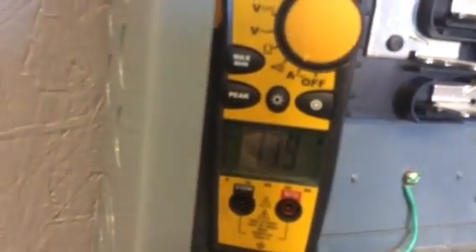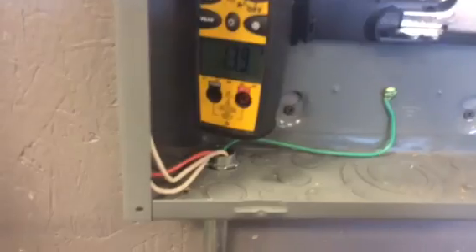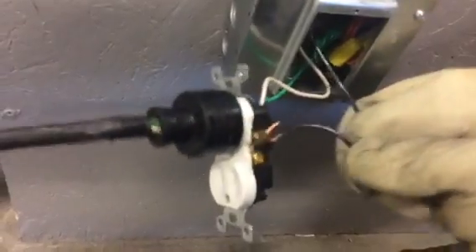You can see the current changing as we're sparking and opening and closing the circuit. We clearly see that it's tied into an arc fault circuit breaker. We're having hundreds of arcs and yet no tripping yet.